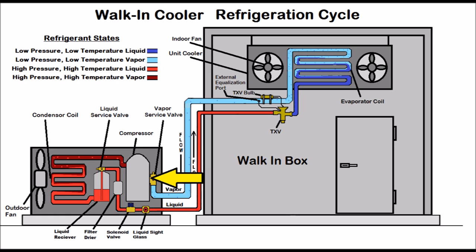You have low pressure, low temperature vapor heading into the compressor. The compressor is located in the outdoor unit, which is the condensing unit. Low pressure, low temperature vapor goes through the vapor service valve into the compressor — you should have vapor only heading into that compressor. Then you have high pressure, high temperature discharge vapor gas coming out. The compressor takes low pressure, compresses it, turns it into high pressure, and since it's high pressure it's therefore high temperature.